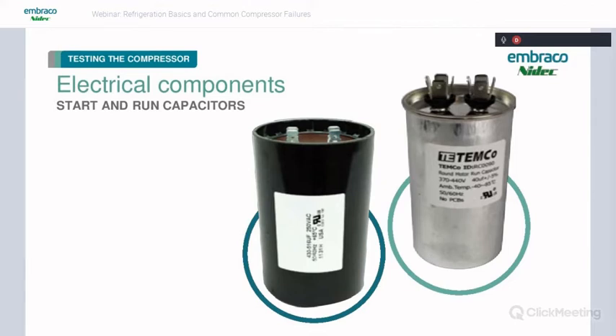And then we have the run capacitor. These are designed to be in the circuit at all times to increase running efficiency. So the way they're designed, they can be energized all the time. And basically, as we stated before, the start winding gives us extra starting torque, and the start capacitor and the run capacitor give us additional running torque and efficiency. And you can check these. The best way to check these is with capacitance on your multimeter. Just make sure that they at least get up to the microfarad range that's stated on the shell, and they should be good. Now, they do wear over time and may not be able to get into the correct microfarad range, so it's important to go ahead and check those whenever you can.